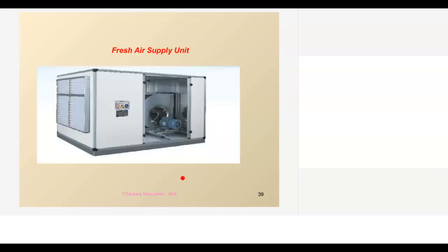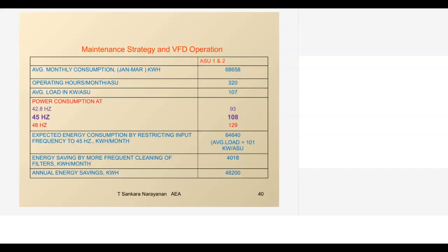See, this is again a case for a fresh air supply unit. The industry has put a fresh air supply unit. The motor is already provided with a VFD. So when the audit was made, we made an observation at what frequency this VFD fan is operating. When we took the readings, initially we took, then every week we started taking it. This air handling unit is monthly consuming 68,000 units. Operating hours is only 320 hours in a month. So 2-shift operation, they are running average 300 hours. The load on the air supply unit is 107 kilowatt.